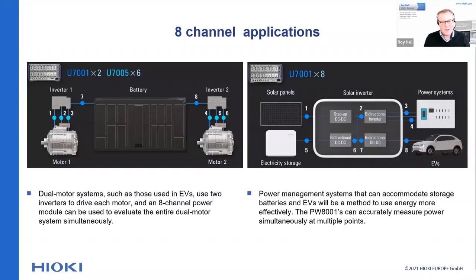We start, of course, with 8-channel applications because the instrument has 8 channels, and that's quite unique in the market. On the left-hand side, you can see a dual drivetrain of a performance EV. In this application, the DC measurement at the input of the inverter can be done with the U7001 input unit. When in future the voltage would exceed 1000 volt DC, this input can still be measured. For the inverter output, however, it's necessary to use the U7005 because of the high bandwidth and accuracy that is essential for the high frequency measurement.